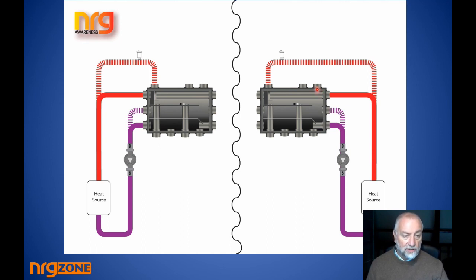I strongly suggest that you wouldn't. You would bring your flow all the way over here so that the water carrying any air will be trapped in the air trap. You could bring it in here and it'll be pulled by the zones as well. It will actually work here. Don't get me wrong, it will work. I would not do it if I had any other choice. I would always try to get the heat over from left to right, whether it's through that pipe or in from the left or into this connection. To my mind, that makes much more sense.